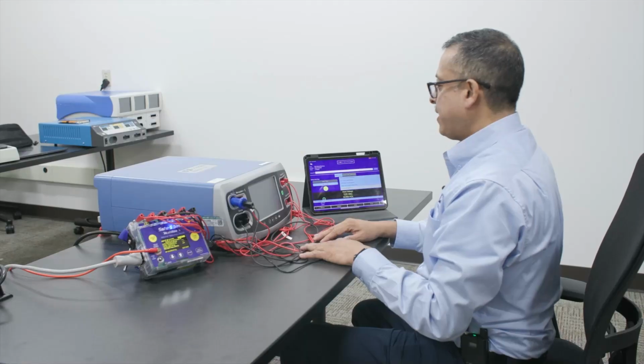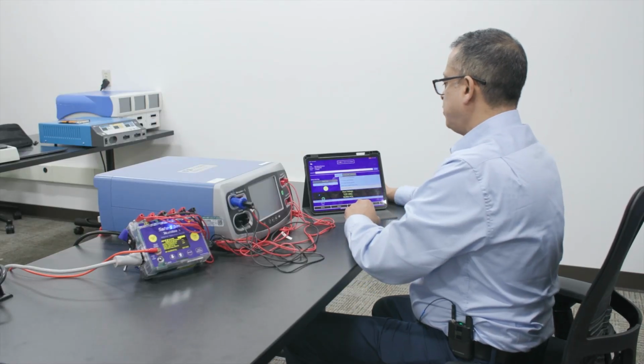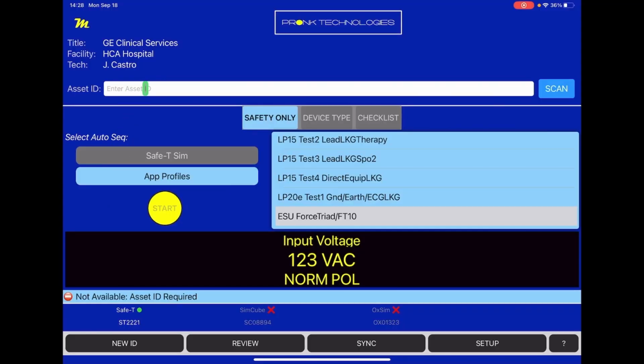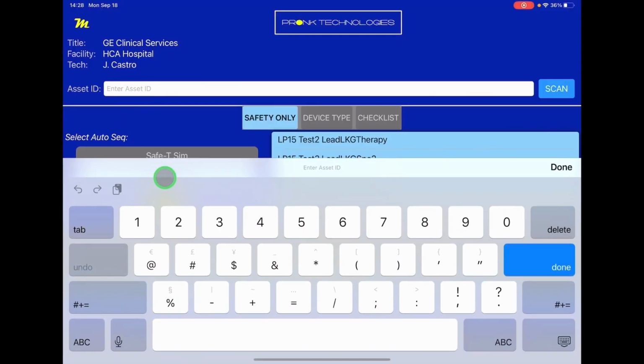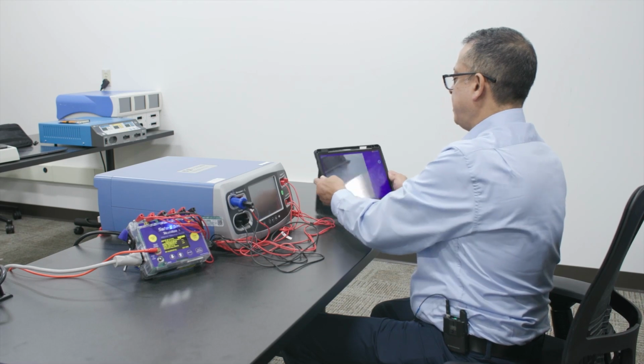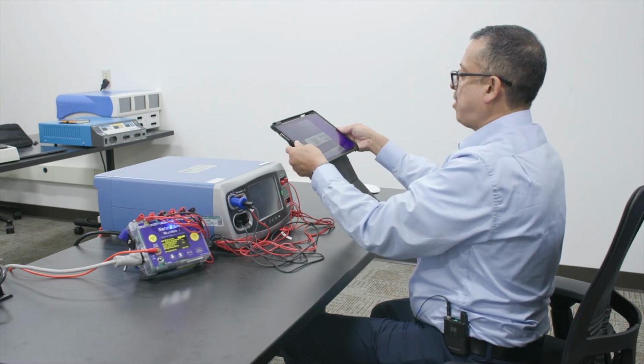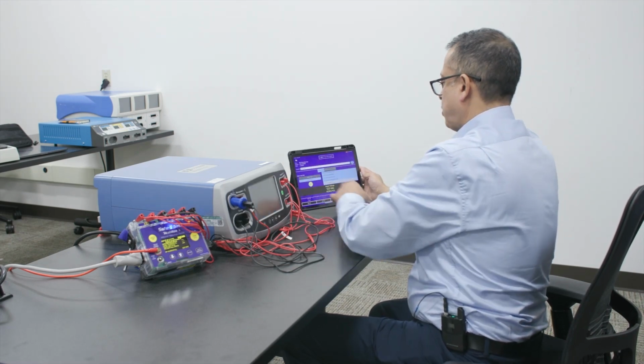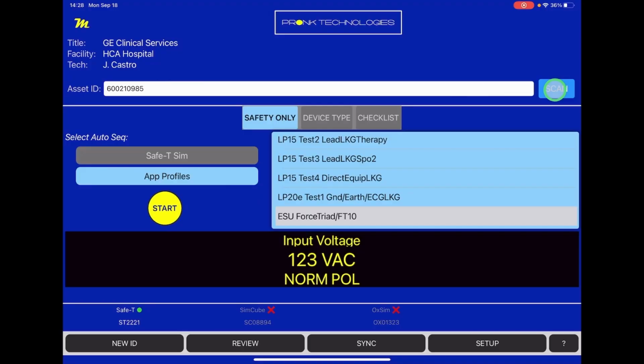So we're ready. The next thing we want to do is go back to the app and start a test. You can do that by tapping on the asset ID field and manually entering the asset ID, or if you have a scanner, you could use the built-in scanner of the Apple device, hold it up to the barcode and scan that asset so we're actually capturing that serial number information. The next thing you want to do is go into the safety only mode and then select app profiles, where we created our electrical safety test sequence, and select it here down below.